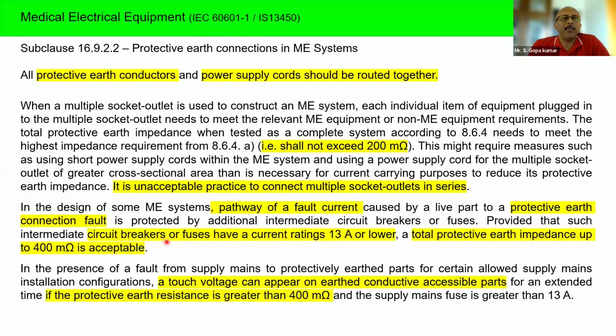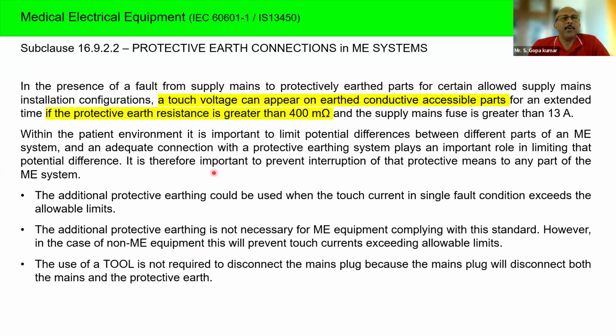You can see here circuit breakers or fuses having a current rating of 13 amps or lower. Total protective earth impedance up to 400 milliohm is acceptable. In certain cases, it is 200 milliohm or sometimes 400 milliohm. Now, a touch voltage can appear on an earthed conductor accessible part if the protective earth resistance is greater than 400 milliohm. So basically, the standard is explaining the efficiency of protective equipotential bonding and the maximum allowed resistances in those particular locations. But the issue is, you can find such explanations in several parts.